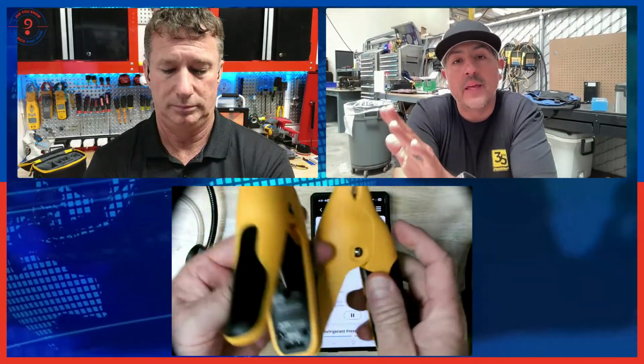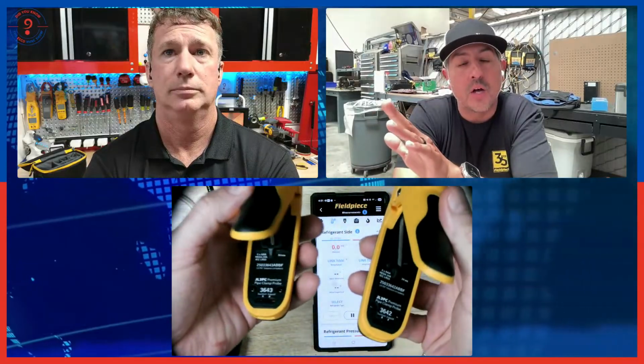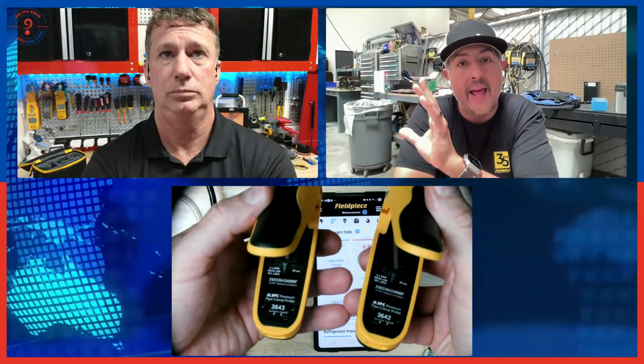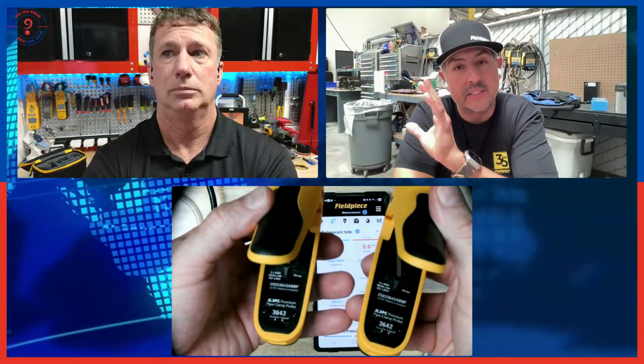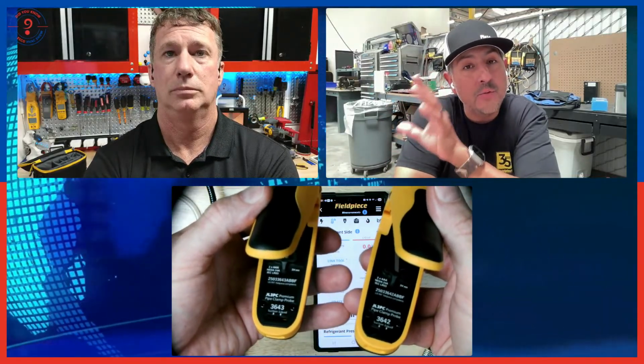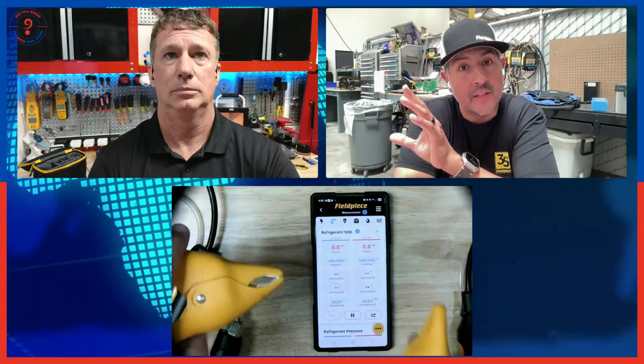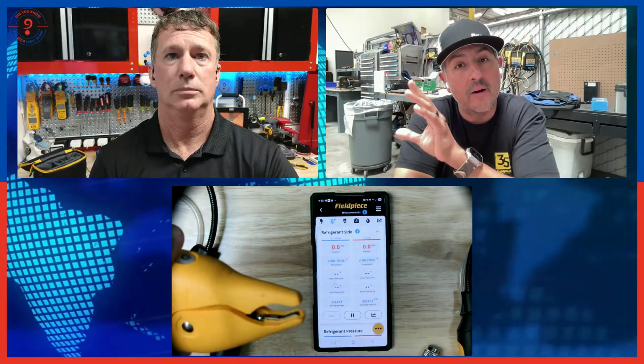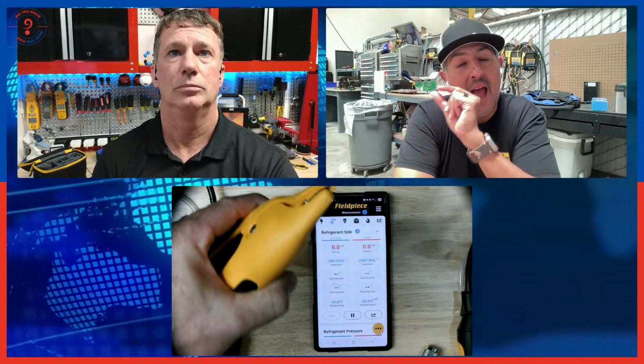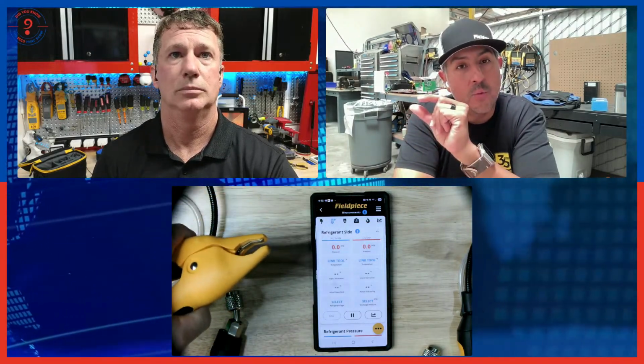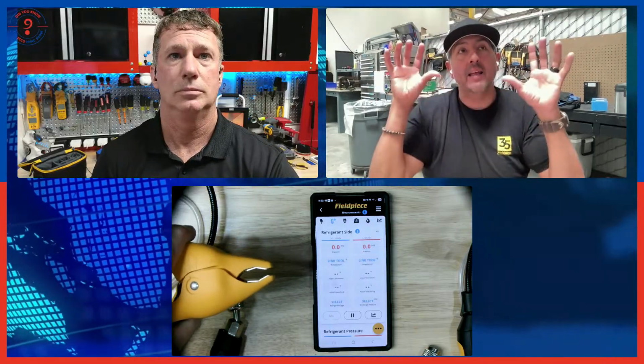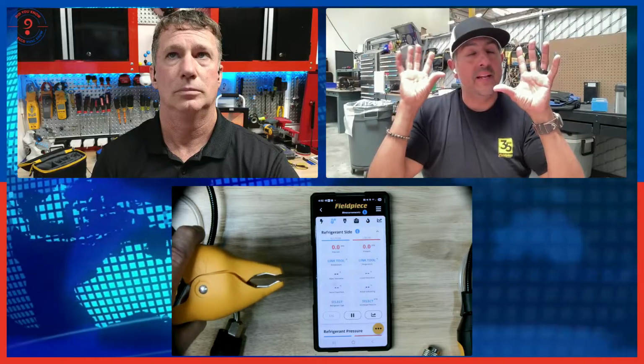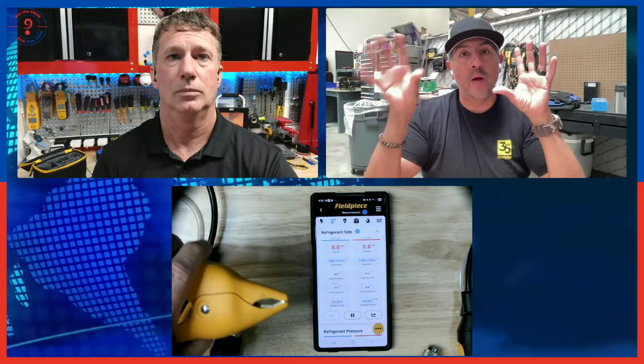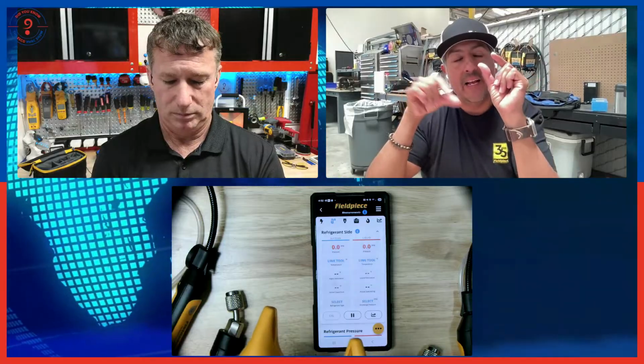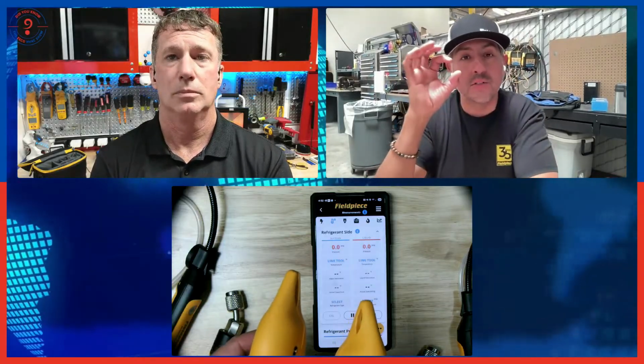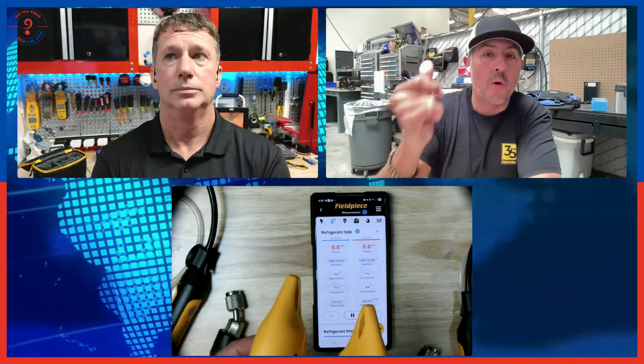Then those are the JobLink pipe clamps, designed to measure pipe temperature, and same thing, they have a switch, one says liquid, one says suction. Those particular pipe clamps are unique in that they have a patented sensor called rapid rail, designed to give an accurate temperature within plus or minus 1 degree on the pipe that isn't influenced by direct sunlight, wind, or moisture, because it uses the conductive copper of the pipe to close the temperature circuit and get a quicker, more accurate reading.